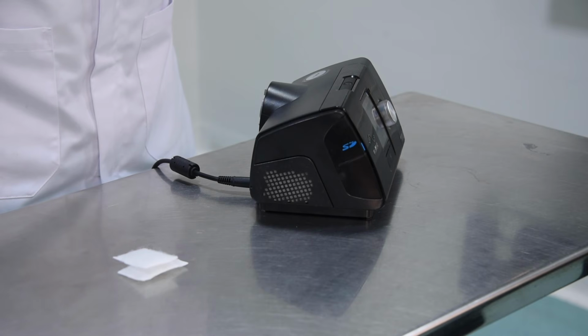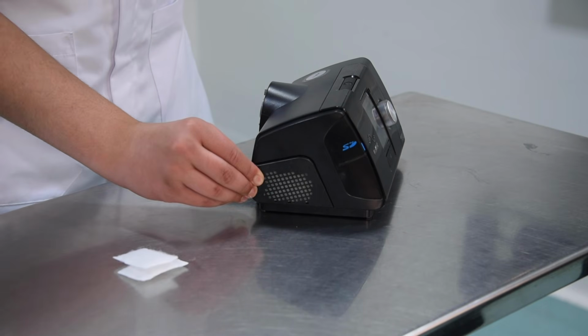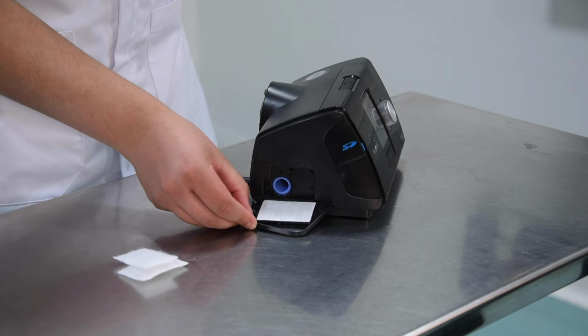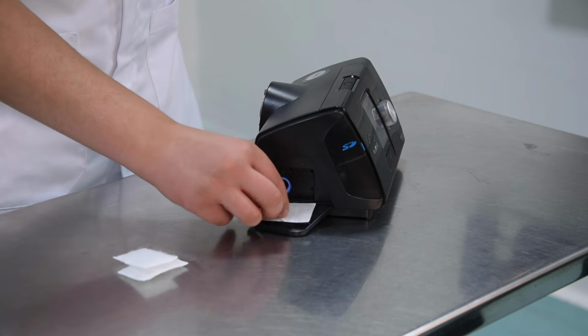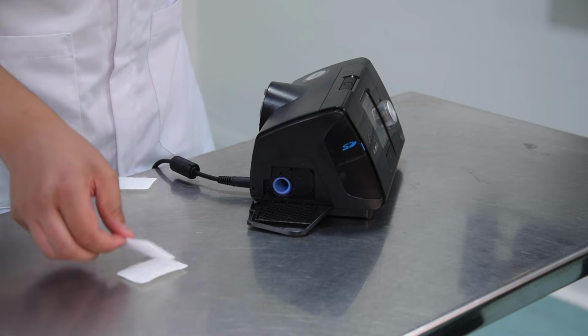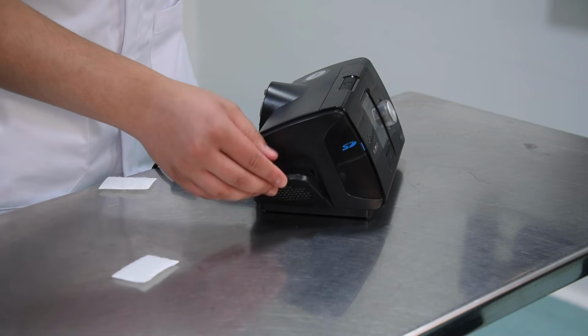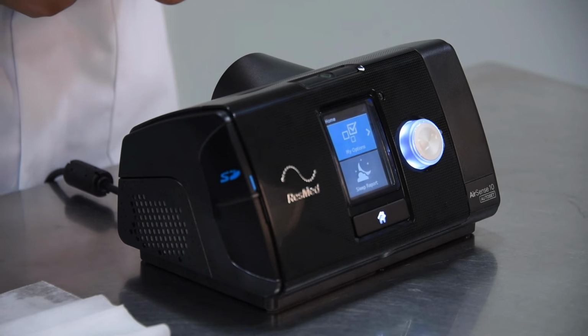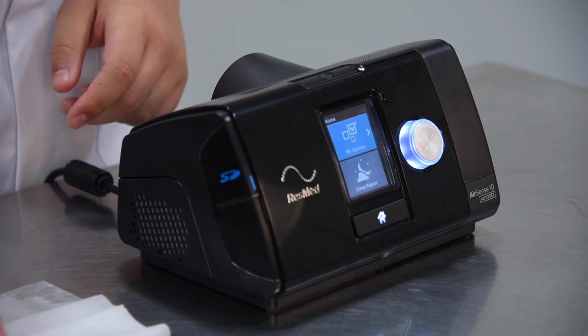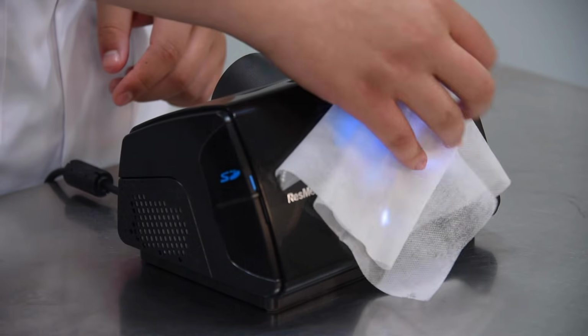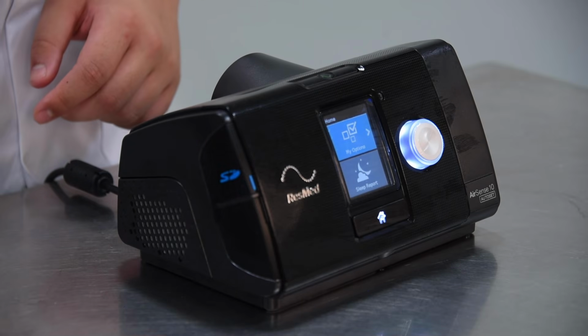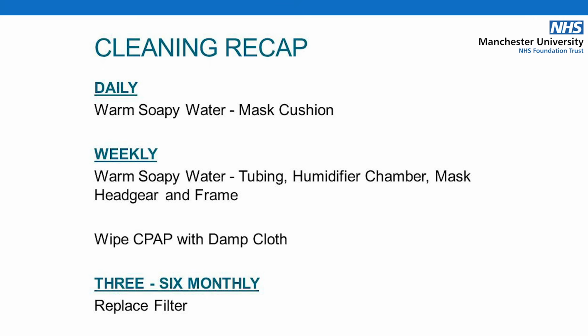The filter needs to be changed every 3 to 6 months. The filter is located on the left-hand side of the CPAP behind the vented filter cover. Flick the filter cover down, remove the current filter, dispose and replace with a fresh filter. Lift the catch back up to finish. Finally, once a week, wipe down the outside of the CPAP with a damp cloth to remove any excess dust. The consumables will last 12 months if they are cleaned routinely as per the previous guidance. As a sleep service, we can provide new consumables every 12 months.